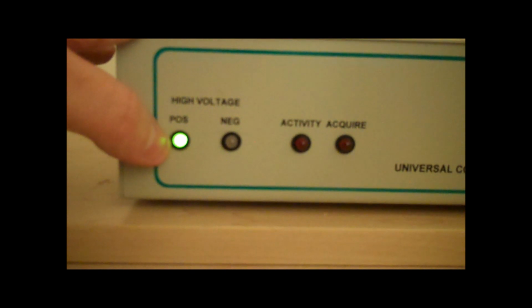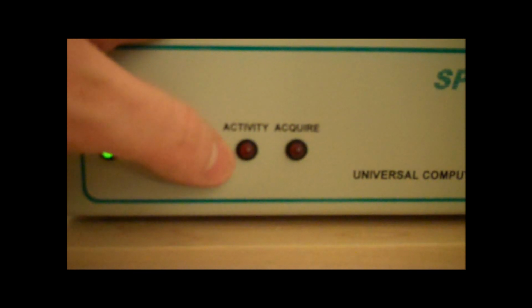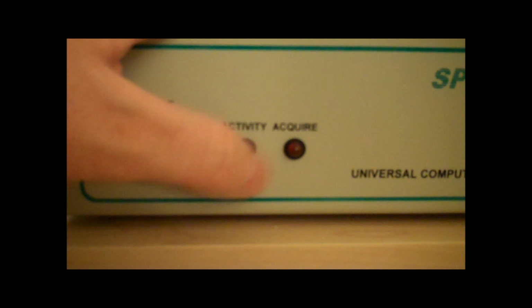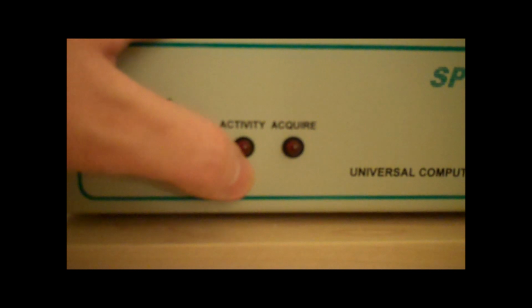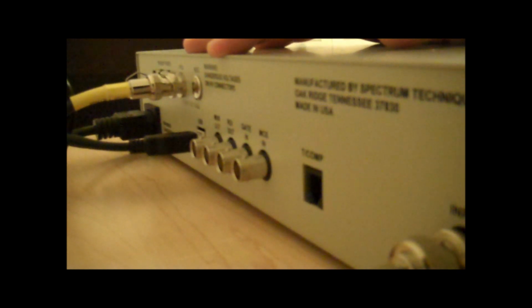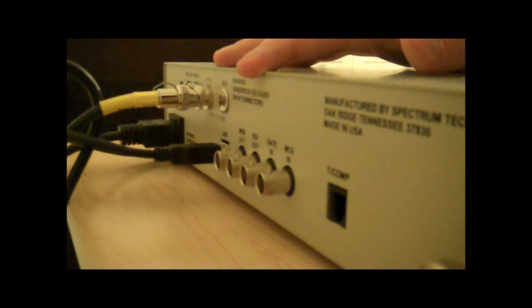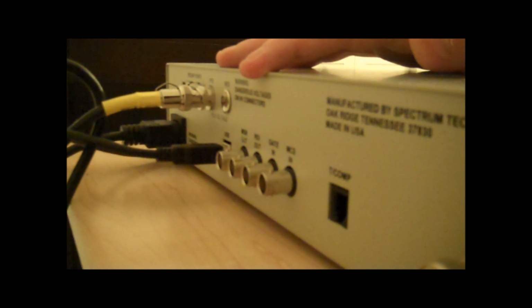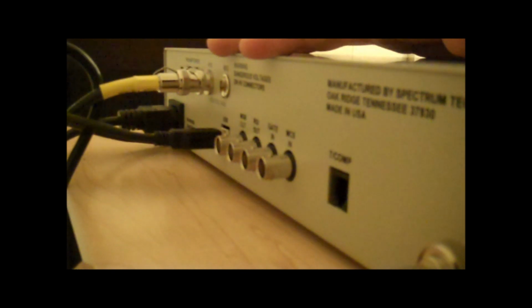It shows its voltage, positive or negative. It shows the activity that's being detected. Each one of these little flashes, were you to see any, would be a count. And it tells you when it's acquiring data. The front is quite simple and straightforward. The back of the scintillation counter is significantly more complex, containing many different devices, many different plugs. For example, this device is capable of connecting to other units to detect things such as muon radiation, using a coincidence circuit and other various devices.